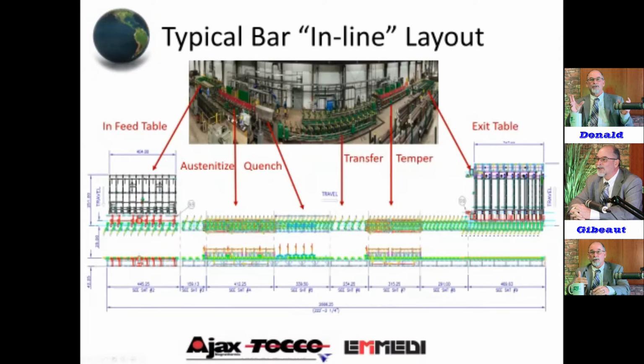And as you can see, everything is driven through here for precise control through the handling. It's critical. And typically we're on 5-foot centers. It depends on your length and your size of tubing for the proper support. Because as you get up in these high temperatures, especially above the magnetic Curie, the plasticity of the tube gets higher. So you have to support it very well to keep it straight and keep it from distorting.